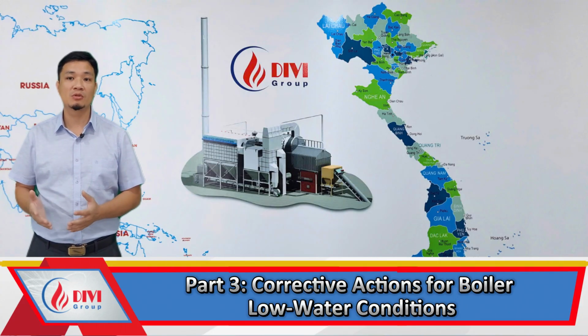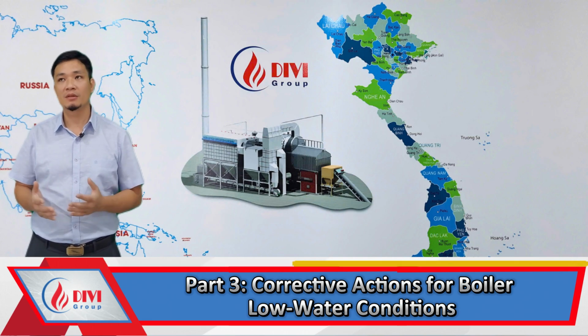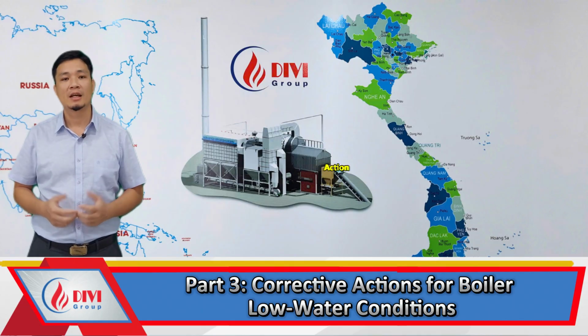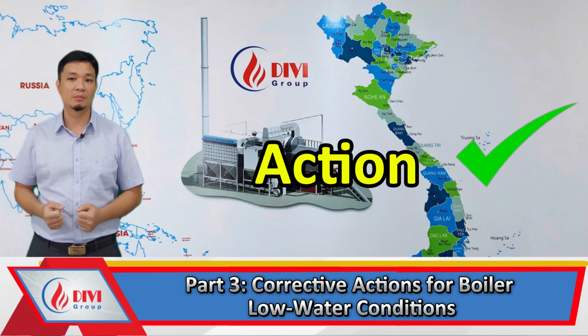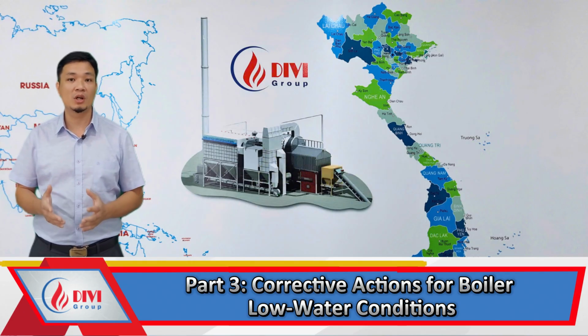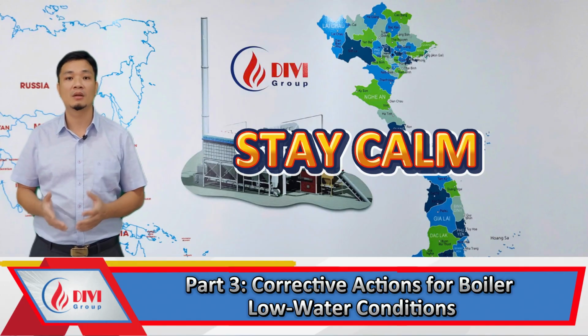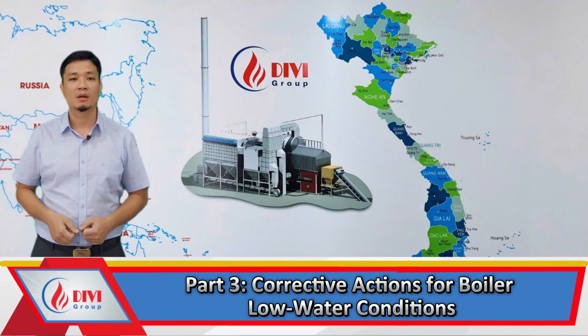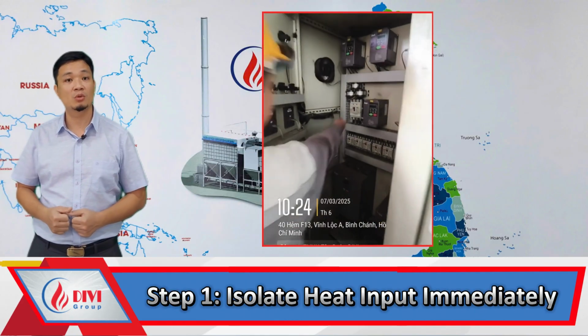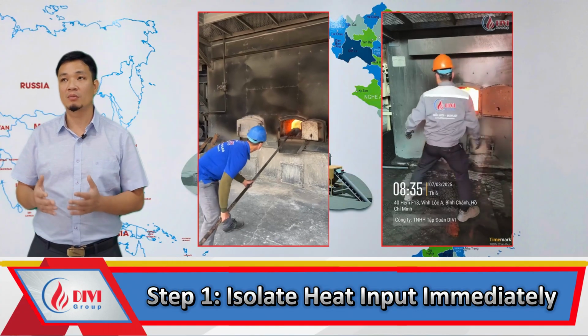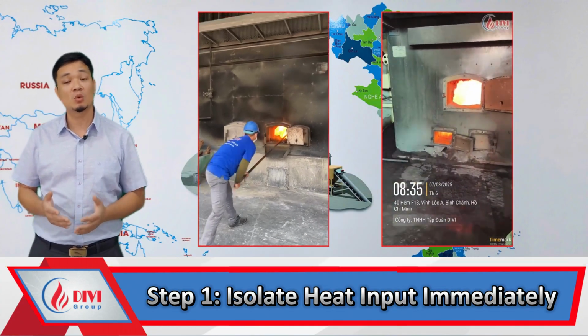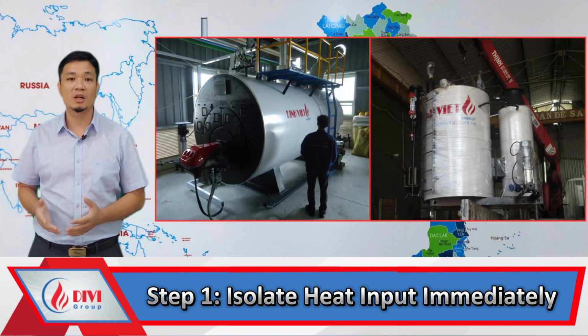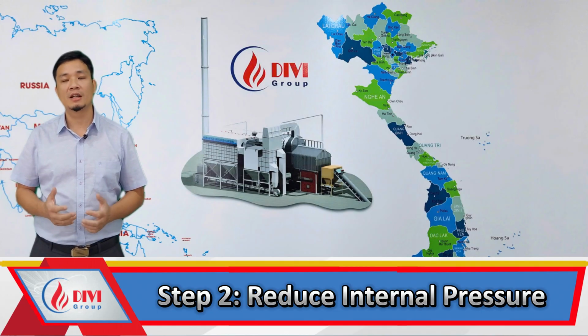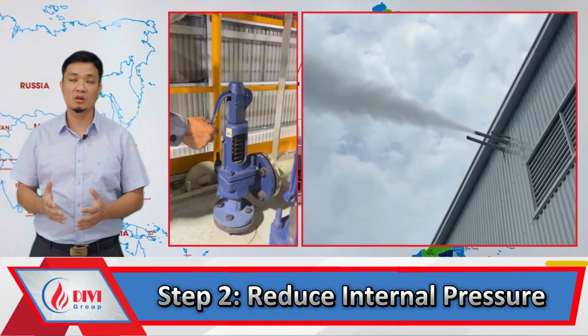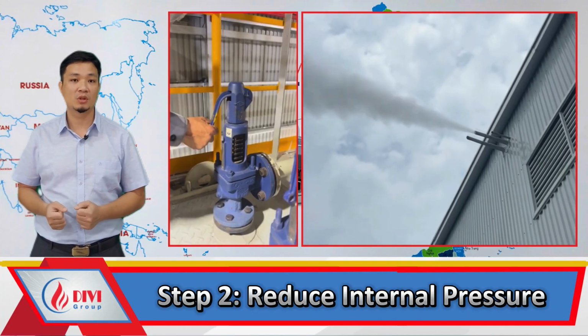Part 3, emergency response. What to do when a boiler runs dry. This is the most critical part of this video. Correct actions can eliminate danger, protect equipment, and minimize unnecessary or avoidable damage. If a dryout is detected, stay calm, do not panic. Follow these 5 key steps in exact order. Isolate heat input immediately. For solid fuel boilers, coal, biomass, RDF, rake out all burning fuel from the combustion chamber. For oil or gas-fired boilers, shut off the burner and fuel supply line. Reduce internal pressure: manually lift the safety valve to release steam and relieve boiler pressure. Open vent valves to aid depressurization and equalize internal pressure to atmospheric level. Diagnose the root cause.